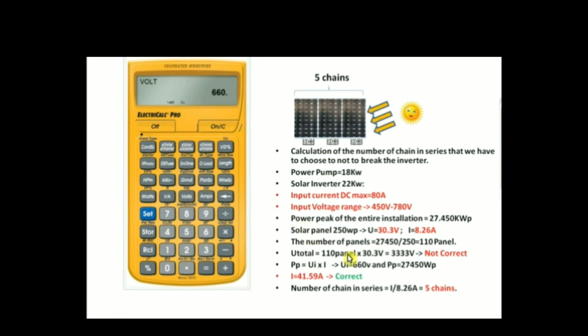We enter the power peak of the installation, which is 27.45 kilowatt-peak. Click on Kilo, then Volt-Ampere. As you can see, we have 27.45 kilowatt-peak entered. Now we click on Amps to calculate the current. The result is 41.59 amps, which is correct because it does not exceed the inverter's maximum input DC current of 80 amps.